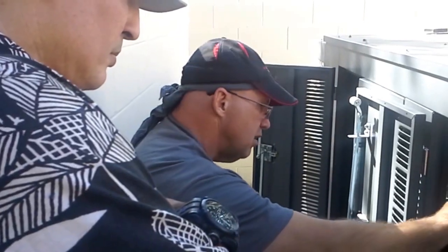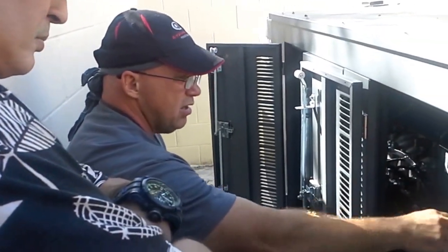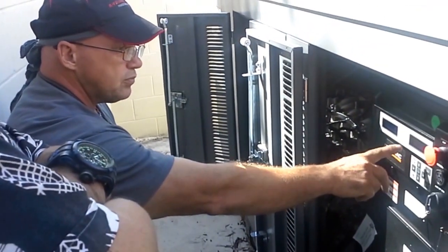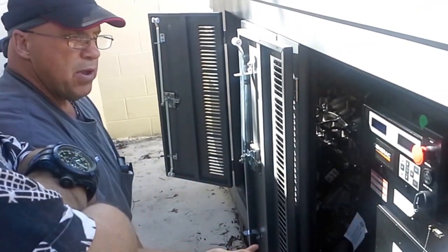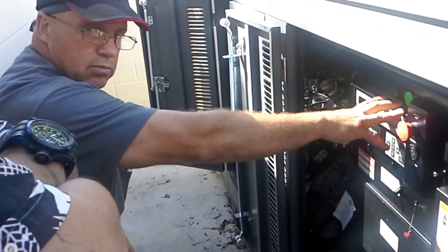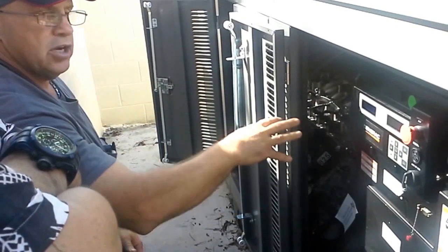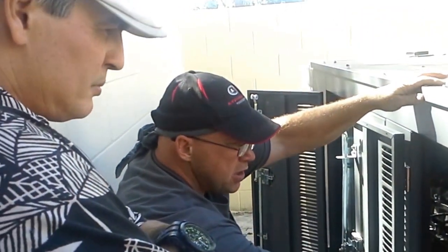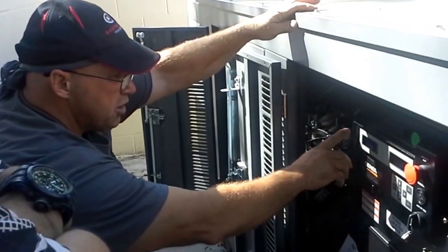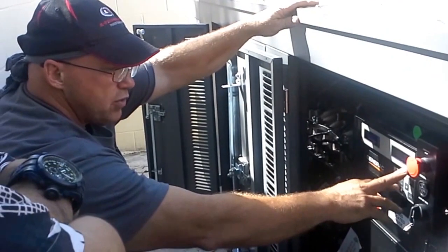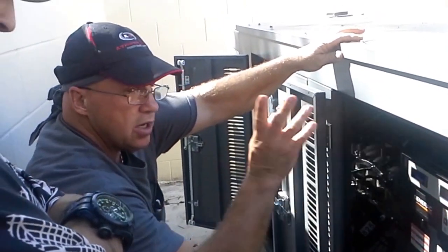Like I said, 99% of the people leave it here, and that's the way I like it as well. And this side here, I would only change this side. I mean, the alarm panel. If you have an alarm, it's going to come up on this side all the time, and it will override any other screen. You can put engine here, your generator, which is this side right now, your diagnostics, exercise, if you wanted to set the exercise from here rather than the ATS.